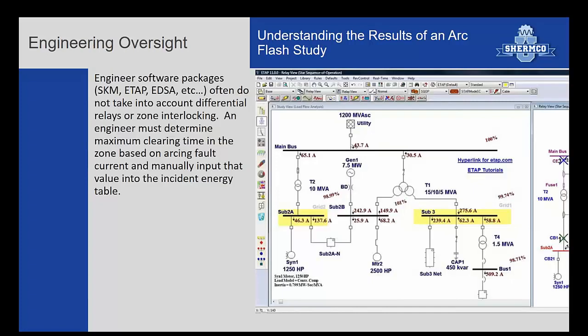So like I was saying, most of the engineering software does not do a very good job if you put in arc flash relays or differentials. There's not really options. It's really looking for circuit modeling, and a lot of times you have to put in an instantaneous relay that just models how fast the arc flash relay would work or how fast the differential will work, to force it into your times. And I know we had a question, Tom, correct, on how do you model?